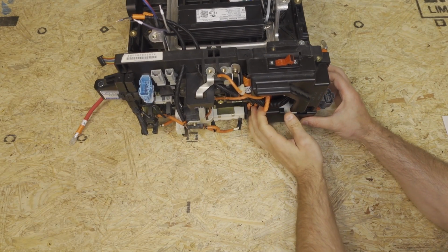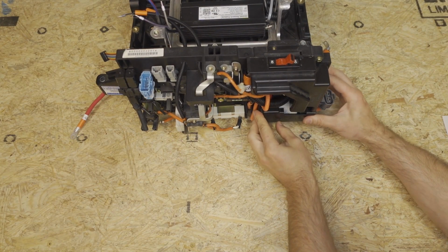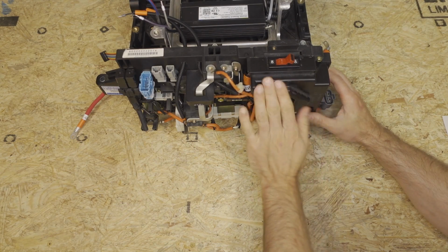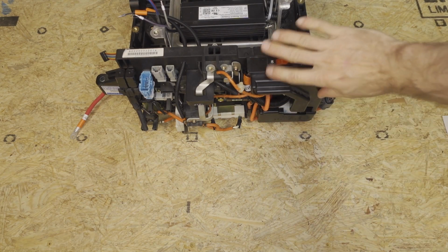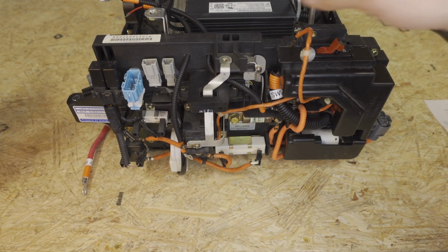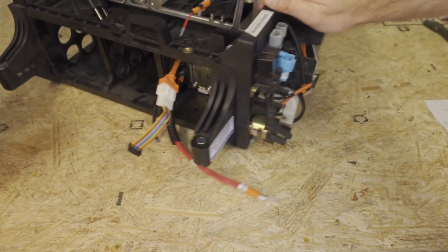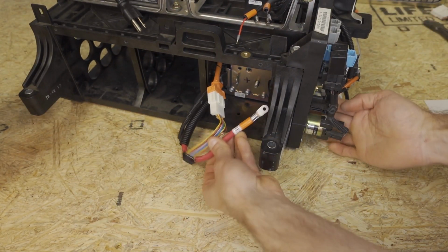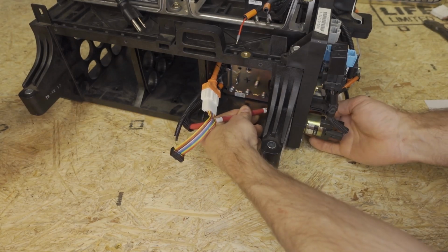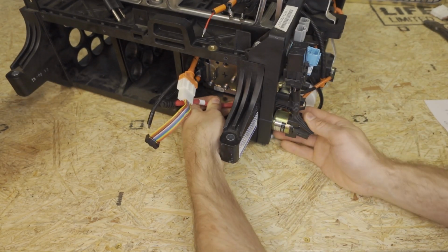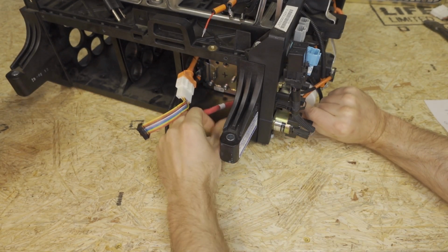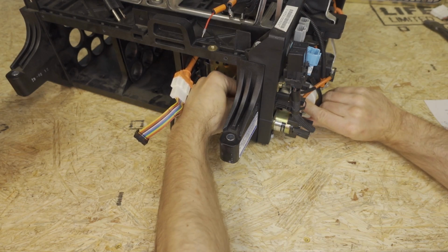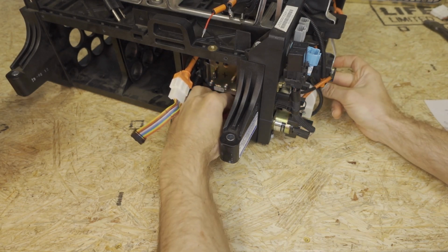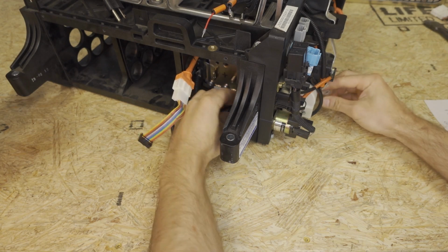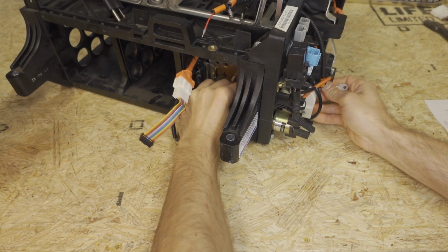The reason we install these covers now is to make sure you don't accidentally touch any of the switched-off bus bars. Next, we take the Bay 1 positive cable and route it through this hole. As it comes through, we turn and route it through the battery current sensor, then pull up as we continue routing.